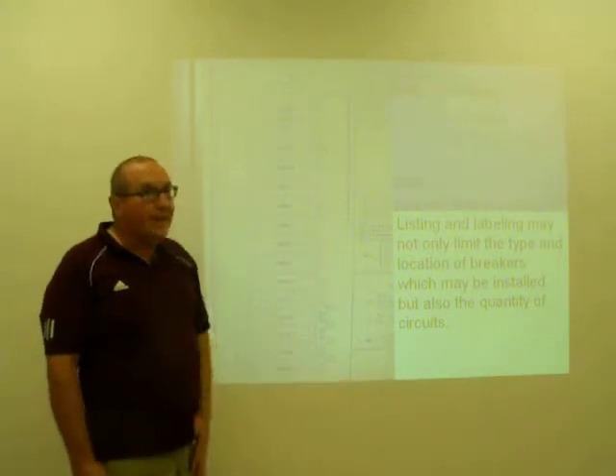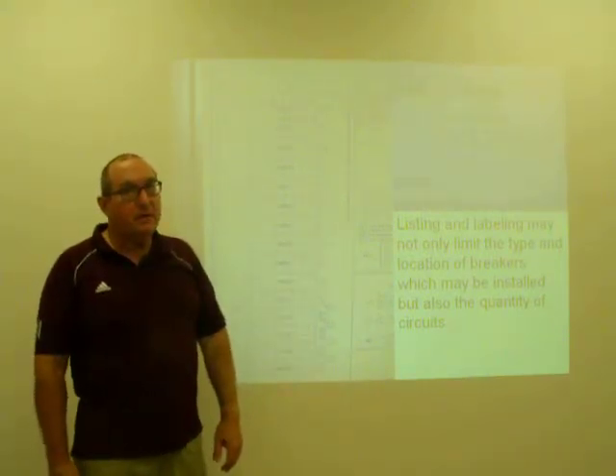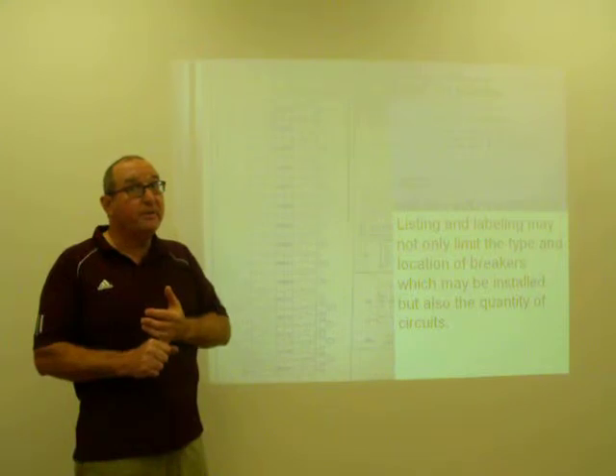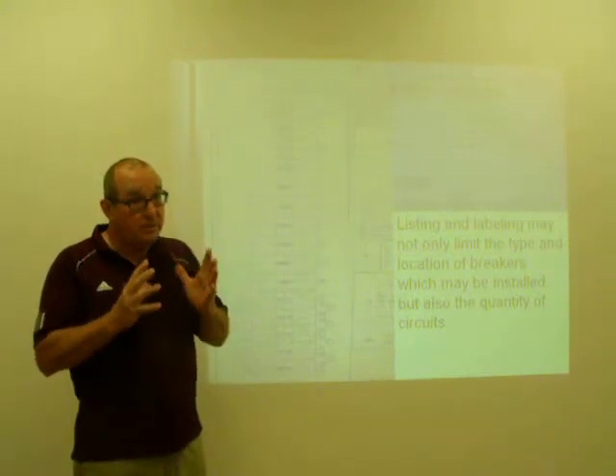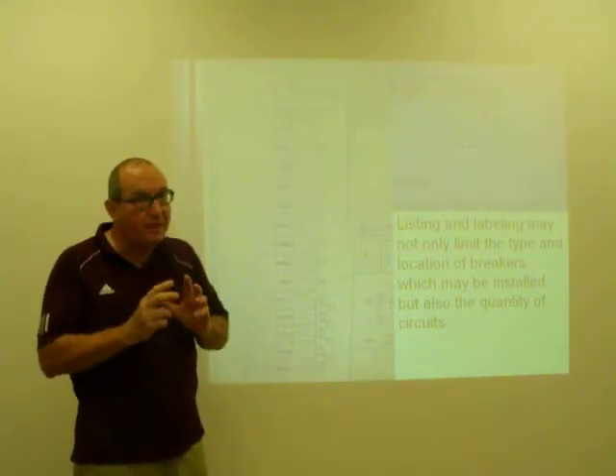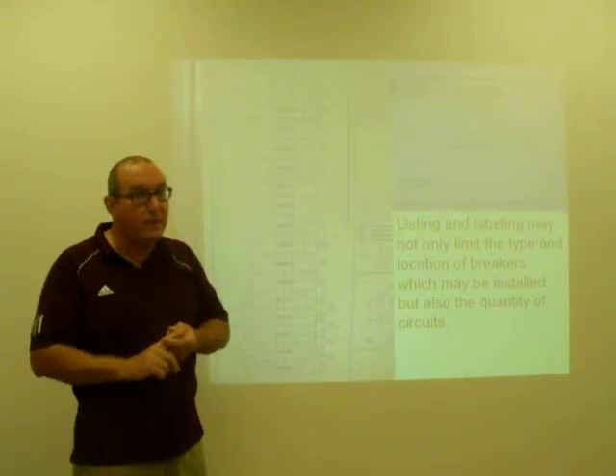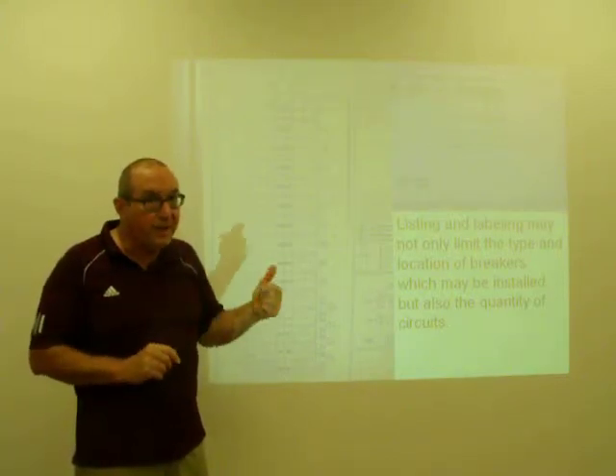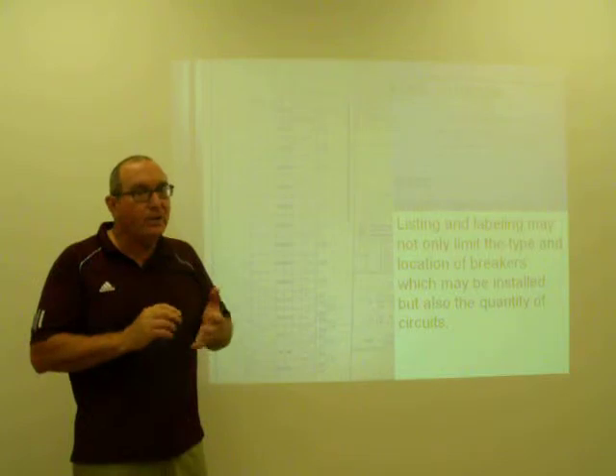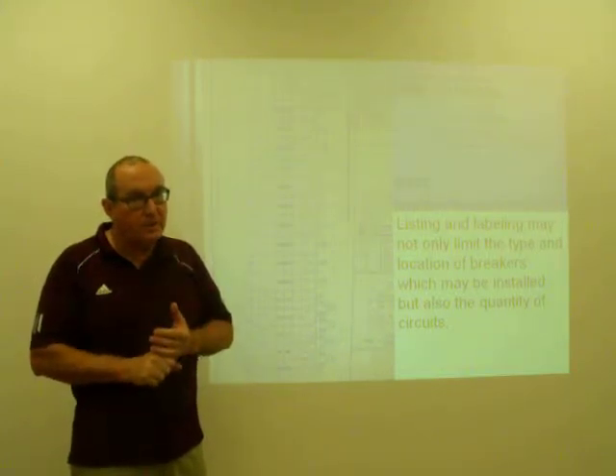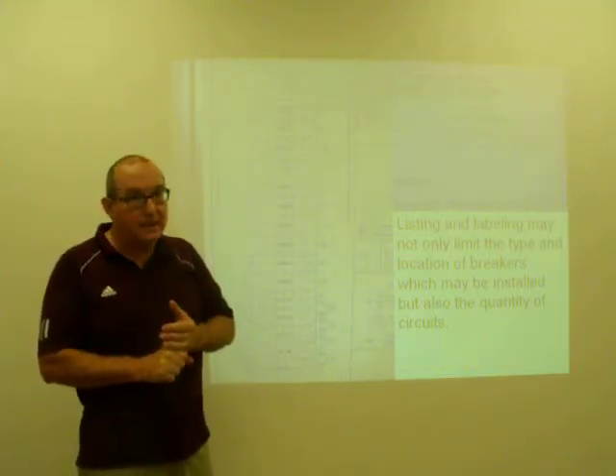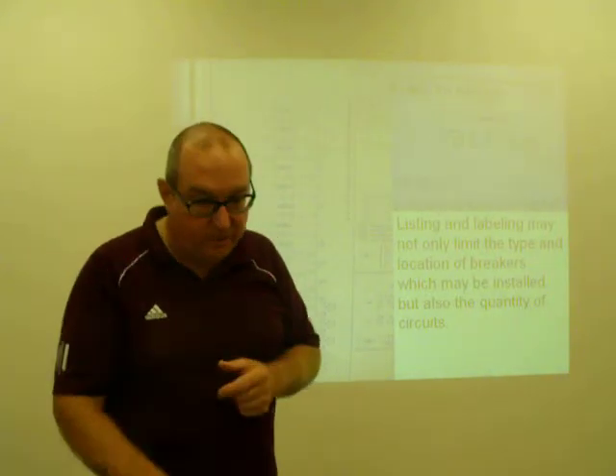So the listing and labeling limits a number of factors. The type of breaker you can install, because certain manufacturers make multiple types that might fit that panel, but only certain ones of those types may be UL listed for that particular application. And the location where those breakers can be installed. And the total quantity of breakers or circuits that can be installed.